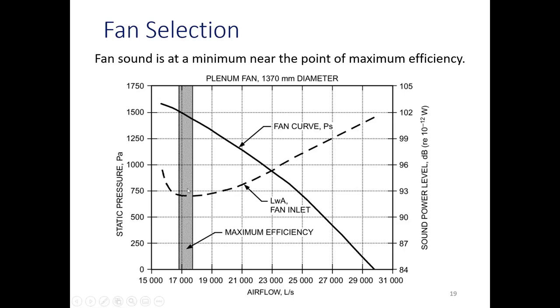And maybe the fan at that point was pretty close to operating in its efficient region. But if you come in and add that pressure drop to it from your silencer, you can shift it out of there and you can make the fan produce more noise. So I'm not saying don't use silencers, because you need to use them all the time. I'm more just saying be aware of that, and hopefully you don't get yourself into a situation where you're chasing your tail, right? You put in a silencer to reduce the noise, but you move the fan out of its efficiency zone, so it becomes louder, so you need a bigger silencer, and you get the picture.